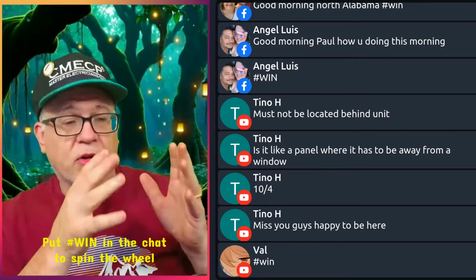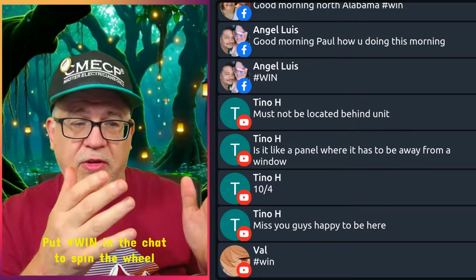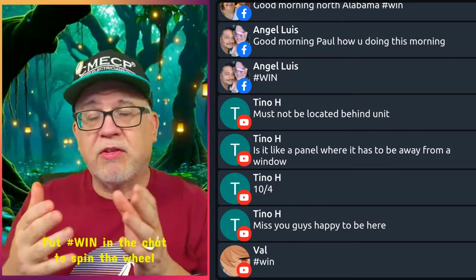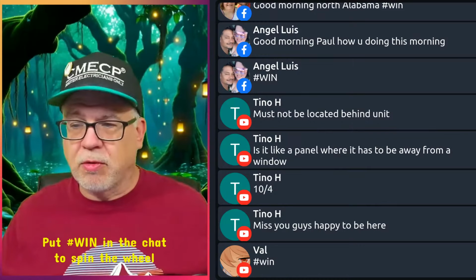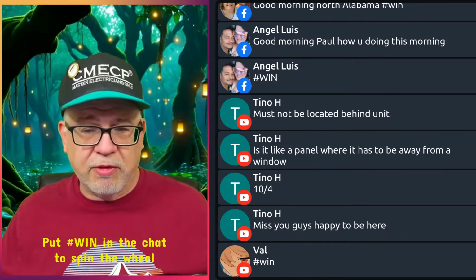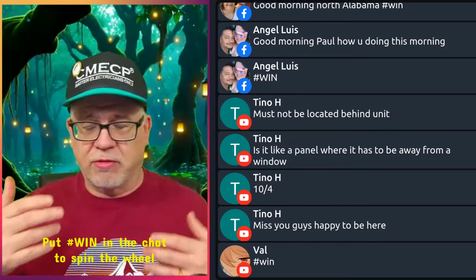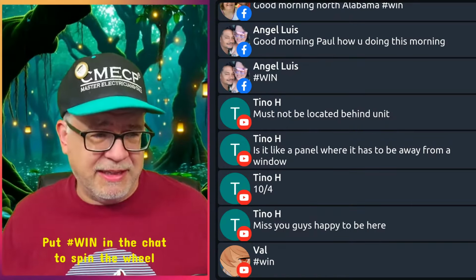So we're putting the fuses or circuit breakers in the ungrounded conductors to protect them from short circuit, ground fault, and overload. But the neutral is typically run to a common solid bus. It could be copper, or it could be some other type of material that's built into the actual frame of whatever the equipment is, and it comes from the manufacturer. So we don't typically have to do a whole lot for anything like that, okay?